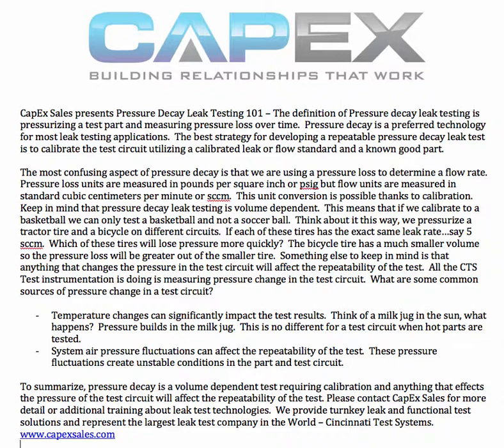The definition of pressure decay leak testing is pressurizing a test part and measuring pressure loss over time. Pressure decay is a preferred technology for most leak test applications. The best strategy for developing a repeatable pressure decay leak test is to calibrate the test circuit utilizing a calibrated leak or flow standard and a known good part.